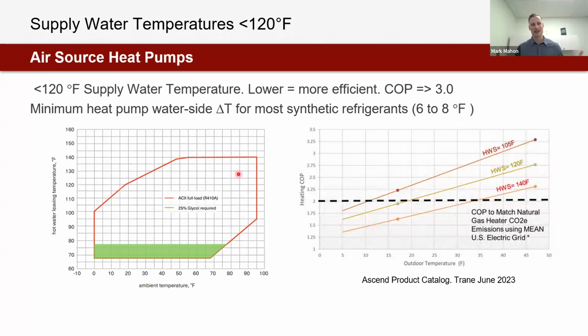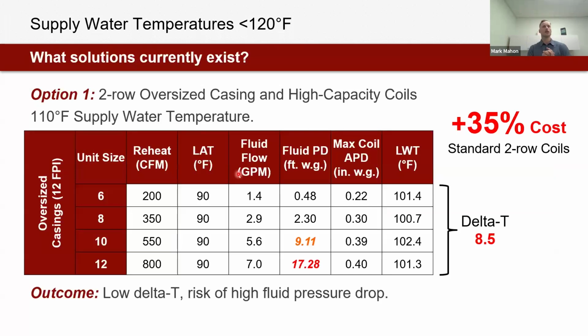Functionally, I don't think there are any boilers that are actually operating at 98% anywhere, but let's say we want to yield like a 95% or 0.95 COP condensing gas boiler. We probably need 120 supply water temperature to really drag that return water temperature down. And so looking at less than 120, this is our same fully optimized coil, the one we just looked at, the beast of a box, the best that we've had historically. How does it operate if we have 110-degree supply water?